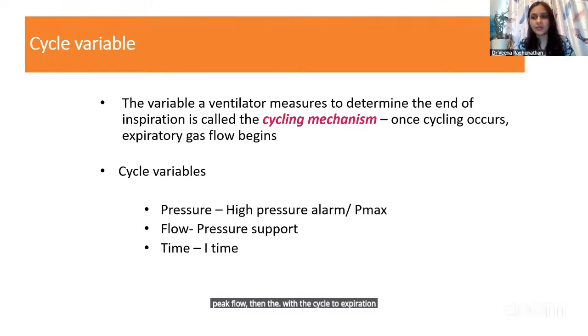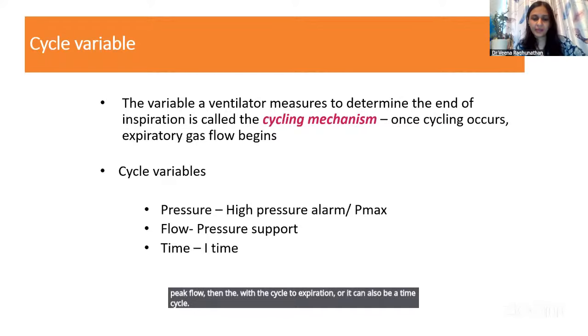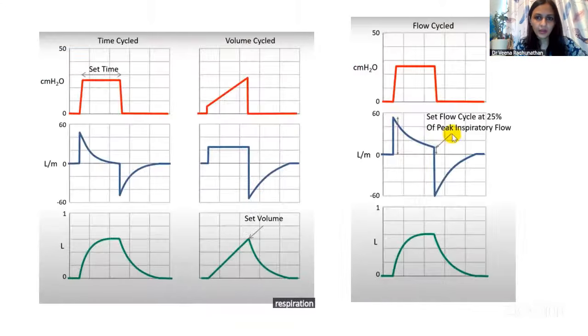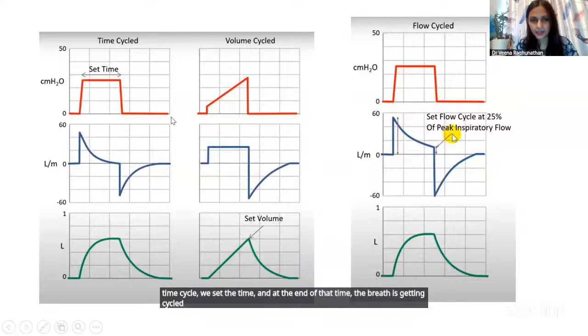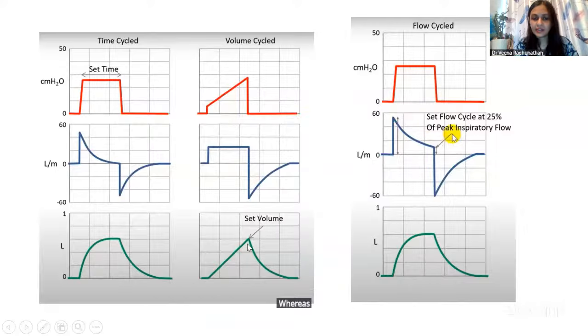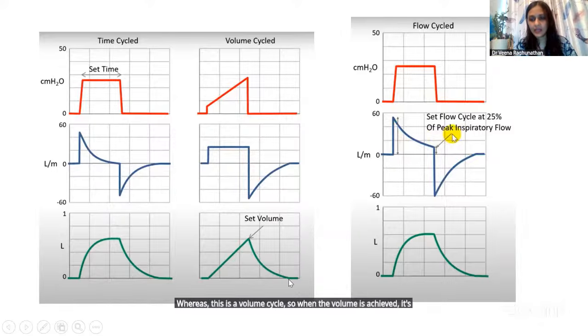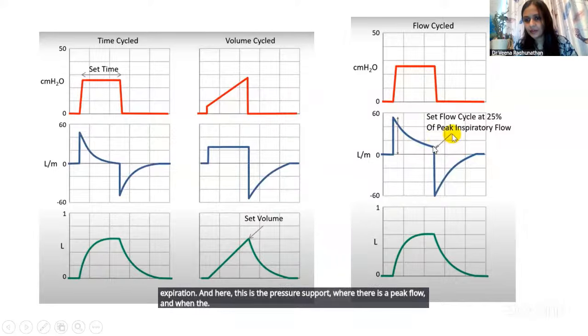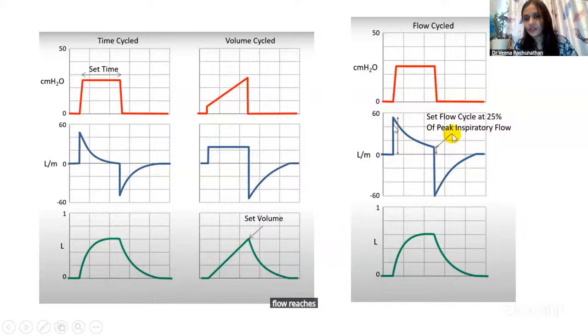Or it can also be a time cycled respiration. So this is showing you the differences. In time cycle, we set the time, and at the end of that time, the breath is cycled to expiration. Whereas this is a volume cycle, so when the volume is achieved, it's cycled into expiration. And here, this is the pressure support, where there is a peak flow, and when the flow reaches some percentage of this peak flow, then it is cycled into expiration.